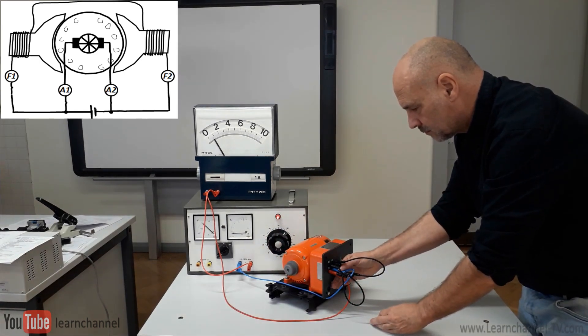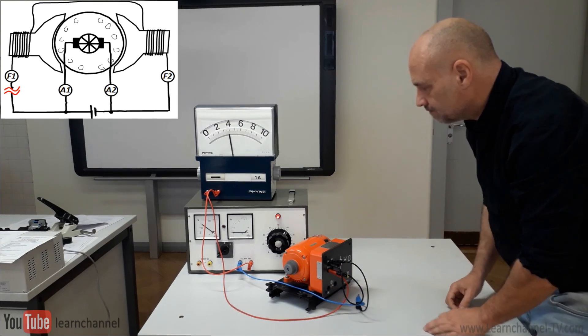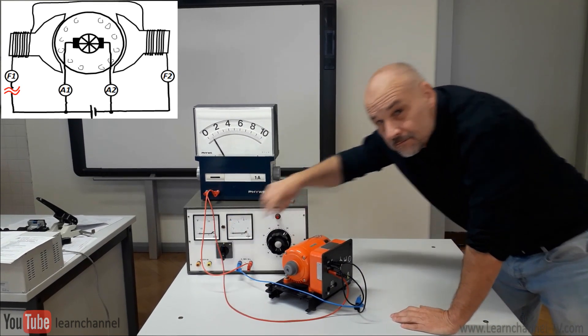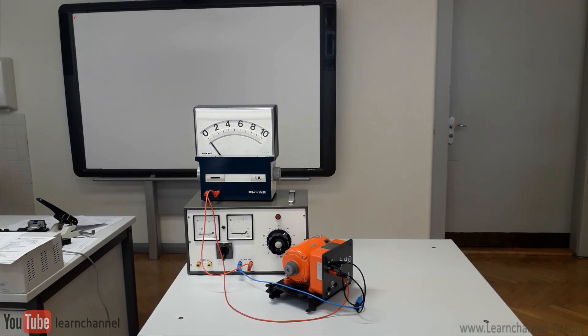If you have a large power supply, the fuses will not blow with the result that the motor will speed up and self-destruct due to centrifugal forces. There is enough torque produced due to remnant flux in the field and a large armature current to accelerate the motor.